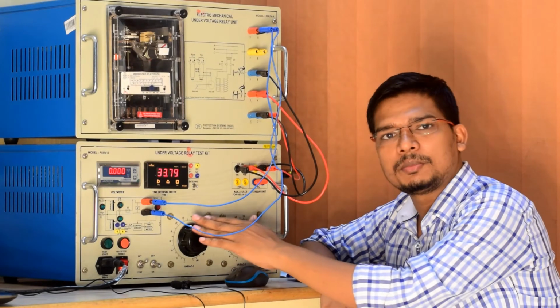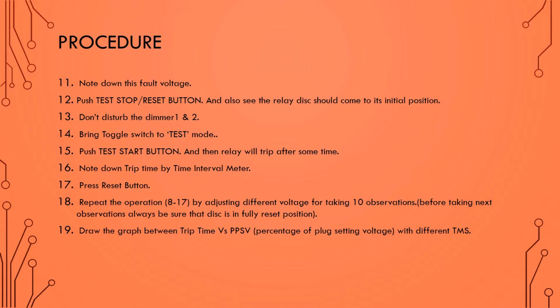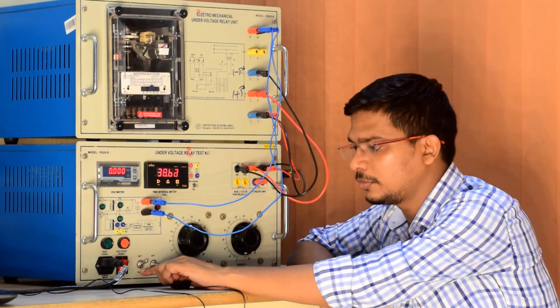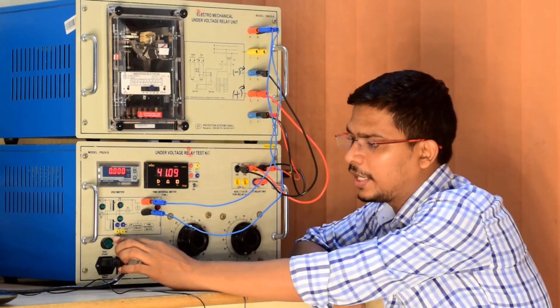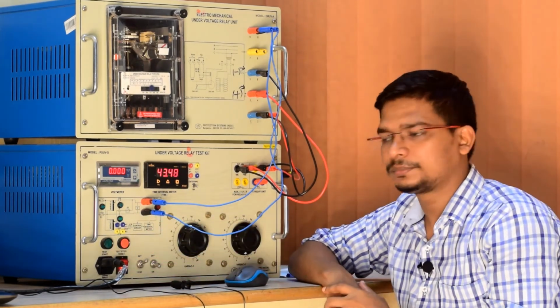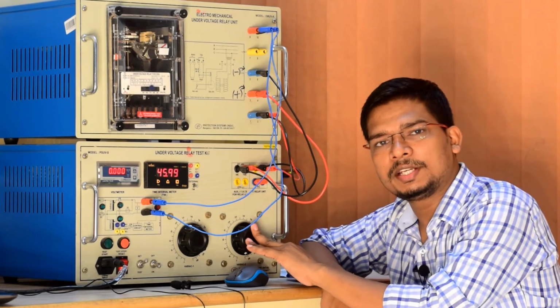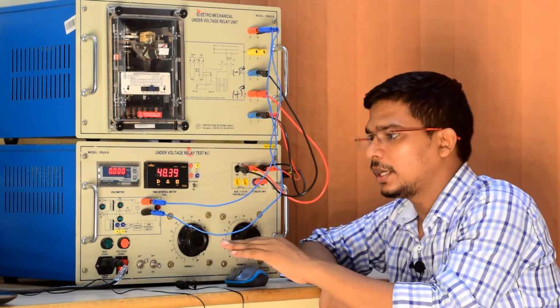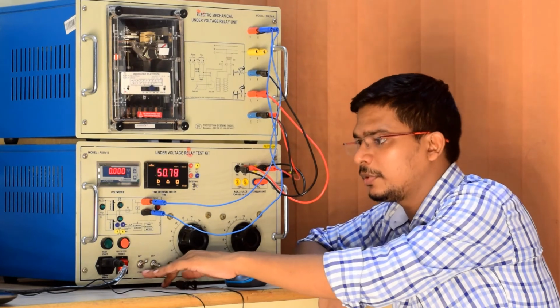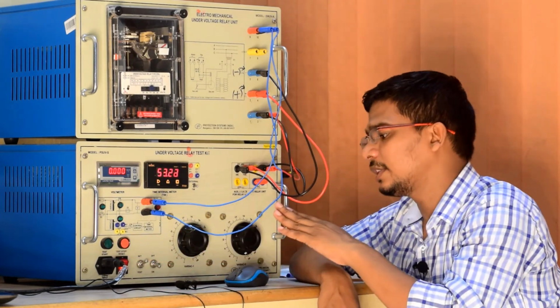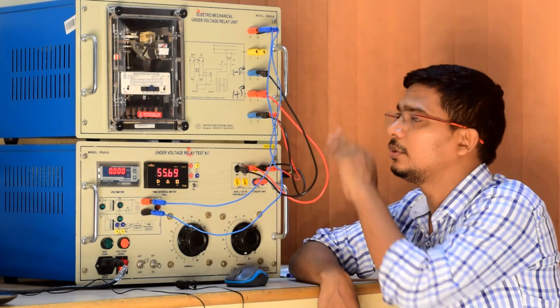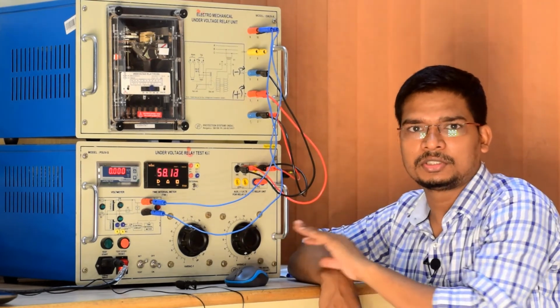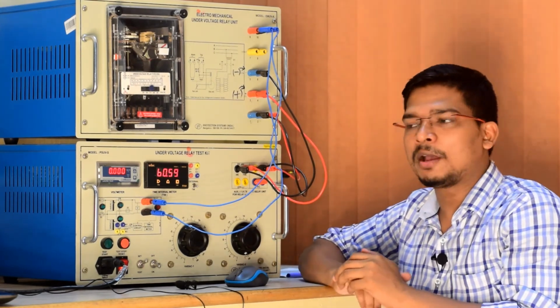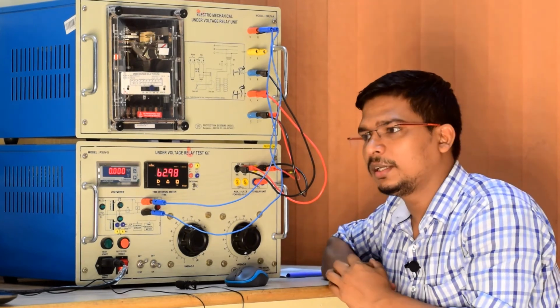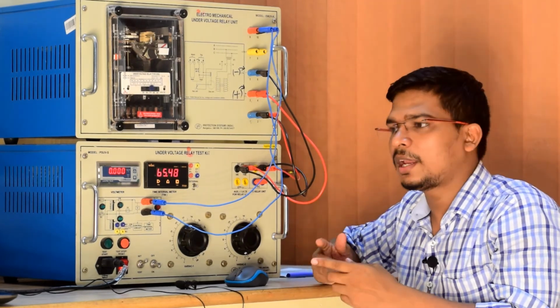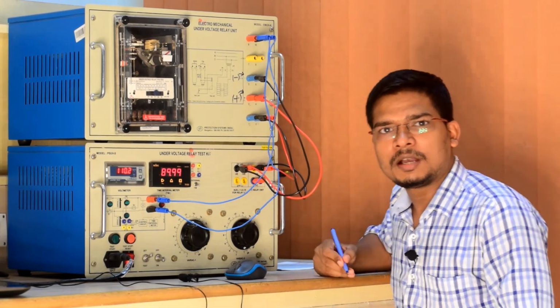Then do not disturb the variac 1 and 2. Then again we have to change the switch to test mode, and after that we have to turn on the circuit breaker again. So whatever voltage we have set during set mode, after changing the position to test mode and turning on the circuit breaker, that much voltage will go to the relay, and the relay will give the trip signal. So this is the process. Now we will go to the observation part, and one by one we will apply the voltage and take the reading.